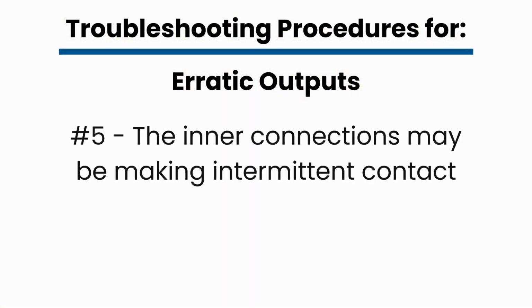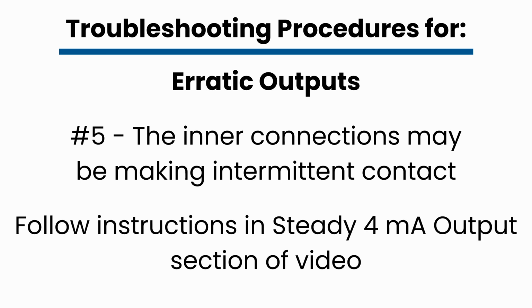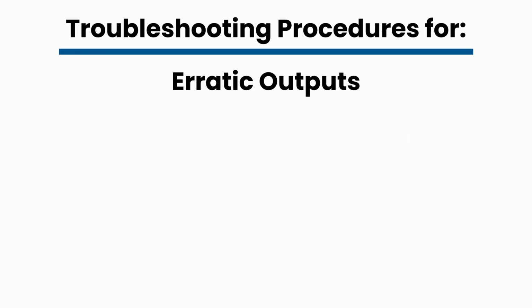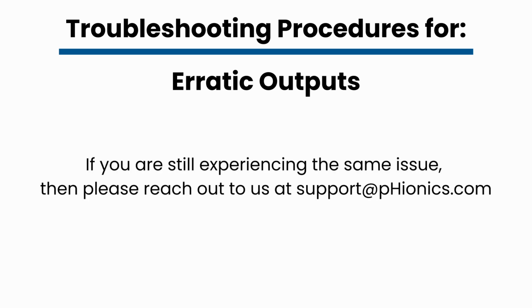Number 5. The cable connector or electrode may be making intermittent contact with the circuit board. Follow the instructions for fixing a steady 4 mA output from earlier in the video. That concludes the troubleshooting section for fixing erratic outputs above 4 mA. If your problem is not yet solved, then please reach out to our customer service at support@phionics.com. On to the next section.